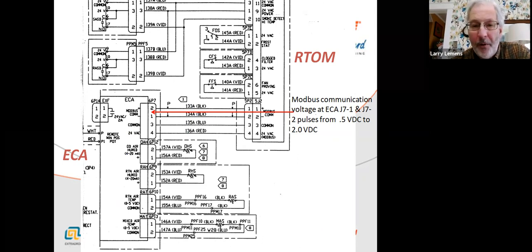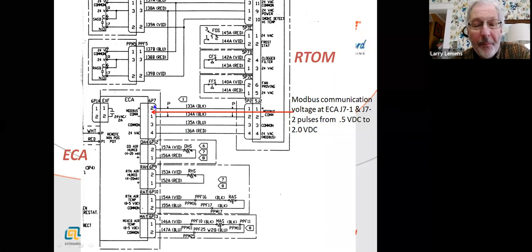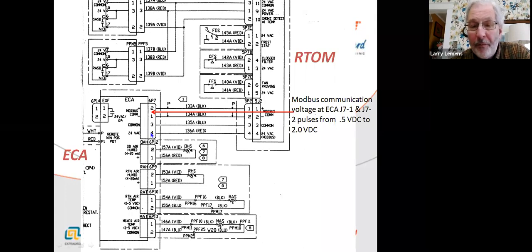So if you've got some unusual things, just do some process of elimination. Turn the power off, unplug the economizer module, flip the power back on. As soon as you turn the power back on, the board's going to see that the economizer is no longer there. It's been taken out of the circuit, and it will operate like there's no economizer there. If the system starts working fine, you've got a shorted economizer. Okay, and this goes back to the microcontrol stuff too.